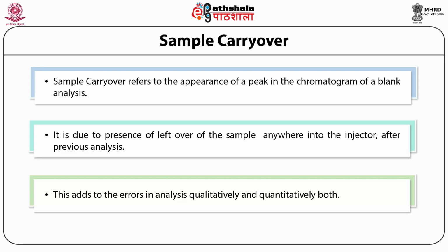To effectively minimize such carryovers, wash solvents are selected judiciously on the basis of sample characteristics. For ionic samples, the wash solution should consist of counterions. For hydrophobic samples that are adsorbed to the interior of the needle or column while conducting gradient analysis, flushing can be performed by pumping a high concentration organic solvent as the mobile phase in the final stage of analysis.